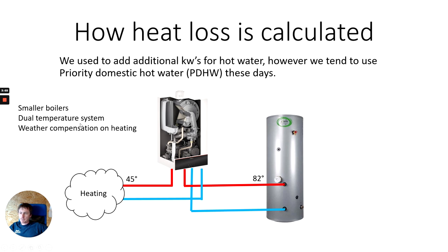With a smaller boiler, dual temperature systems, and weather compensation on the heating, we heat the cylinder up quickly at a higher temperature and then revert back to a lower temperature heating system to match the heat loss for that given day. The cylinder gets heated to 60°C with a flow temperature of around 65°C to kill any bacteria and legionella.